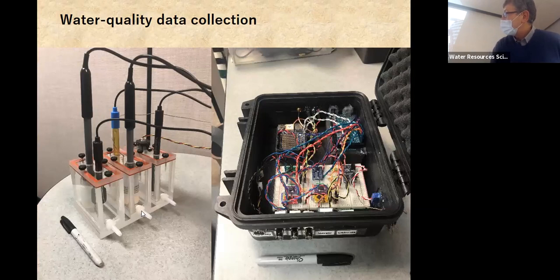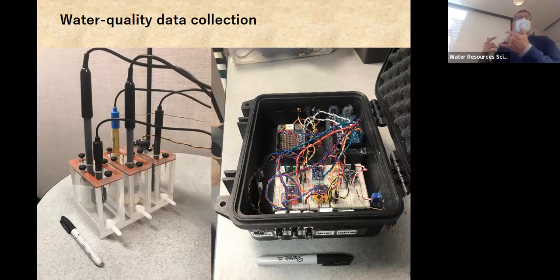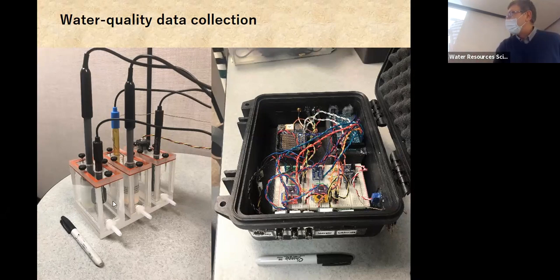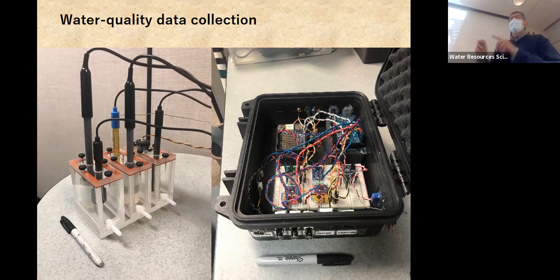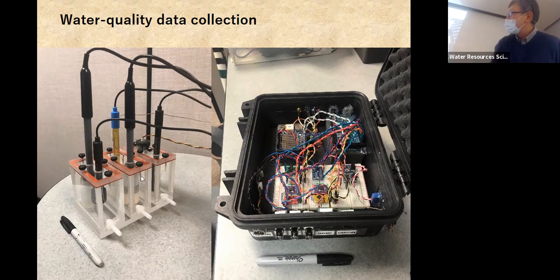The nitrate and chloride ion-specific sensors didn't perform well in the field — they may have worked in a lab, but we gave up on them. We also had a problem where all the probes interacted: the resistivity probe would affect the chloride probe, which would affect the nitrate probe. Our solution was three flow-through cells in series with a little brass pipe between them that we grounded to electrically isolate the probes.